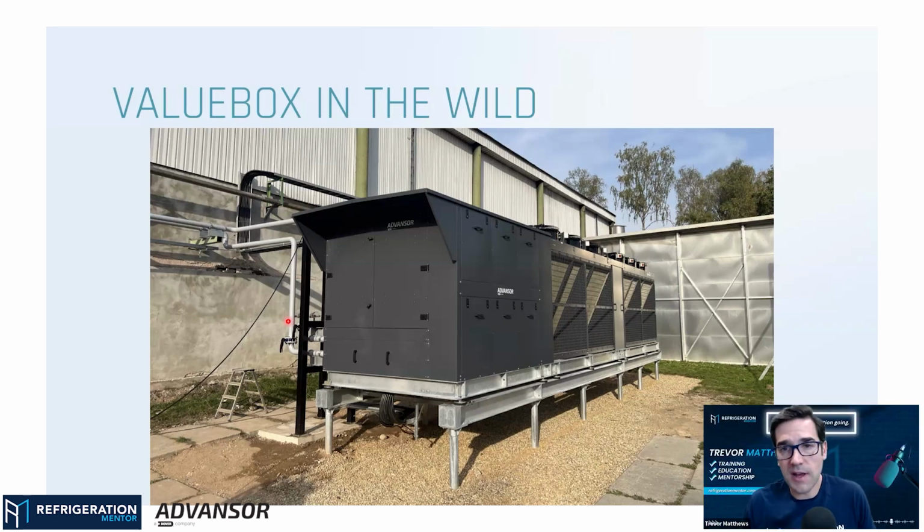So slow startup, that's any system anyway, any CO2 refrigeration system, or even a supermarket rack. We just got faster at doing it. We're just used to working with HFCs for years, so you got faster and faster. Now this is with CO2. Every system is a slow startup, right? You turn some systems on, make sure they're working well, then go to some more. It's the same with this. We don't want to just bang everything on. It'll run into more issues.